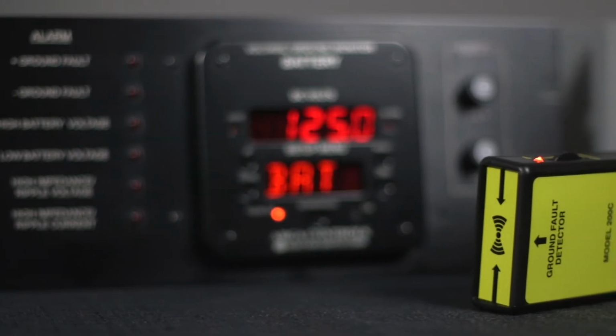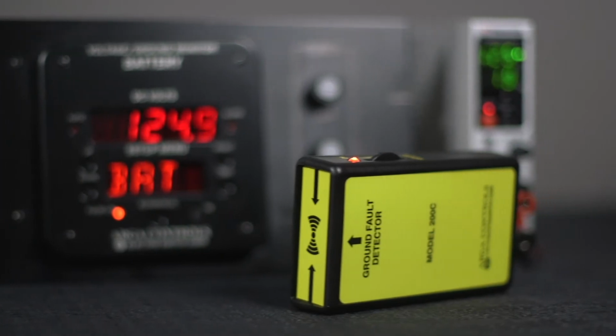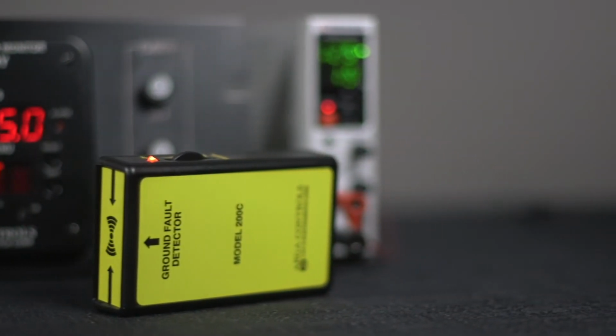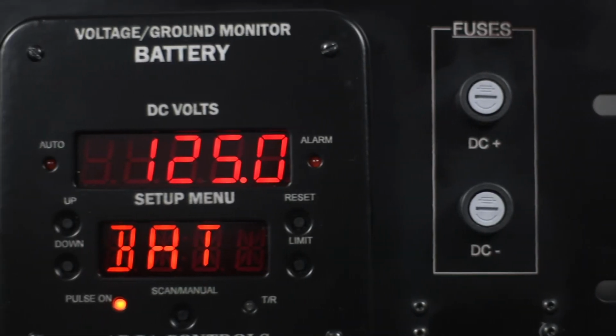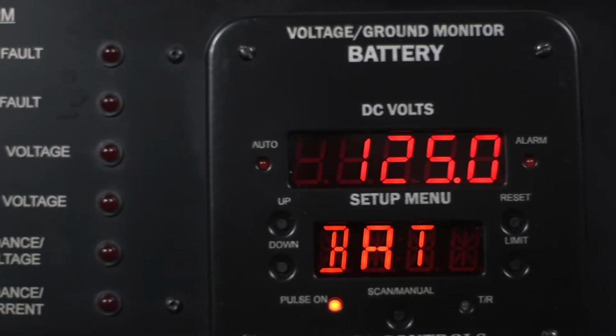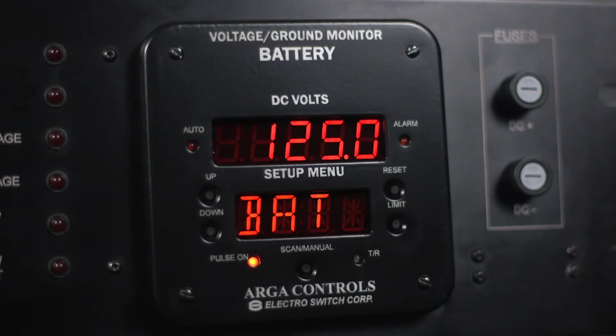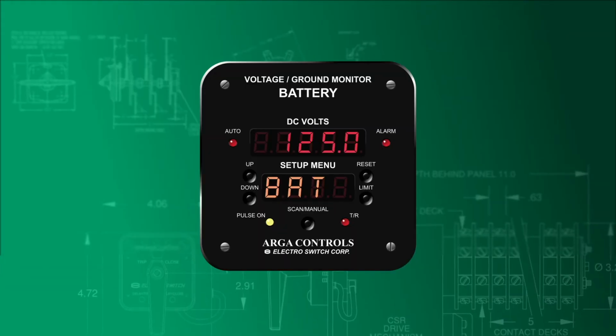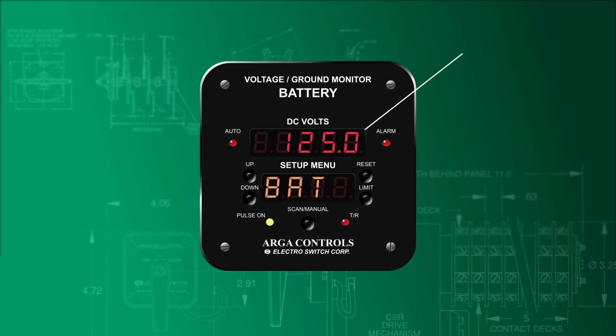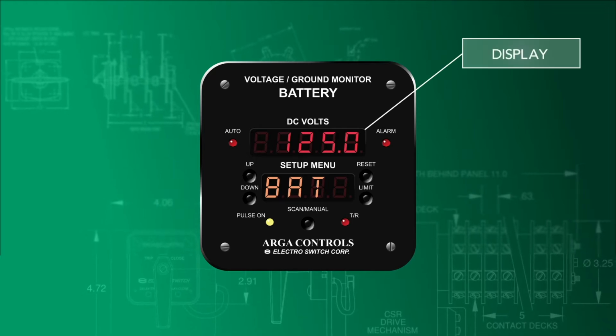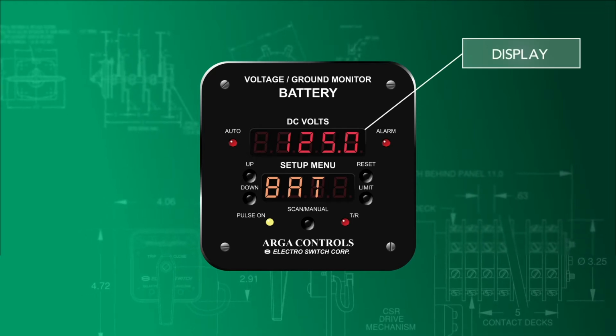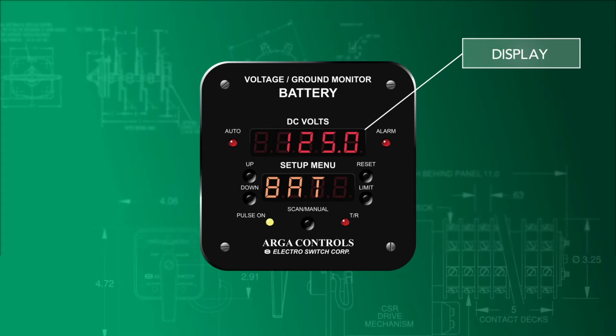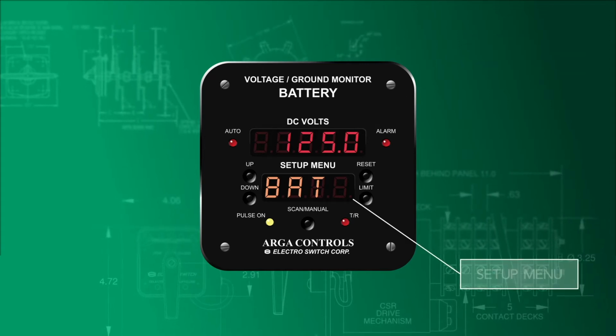For our purposes, I will be demonstrating a 19-inch 4U rack-mounted model 15-1000-125A-1 with single battery monitor for 125 volt DC systems. Presentation of the battery monitor display. As you look at the front of the battery monitor, you can see two windows. The upper window displays voltage, time delay, and phase selection of the AC chargers. The lower window displays the setup menu.